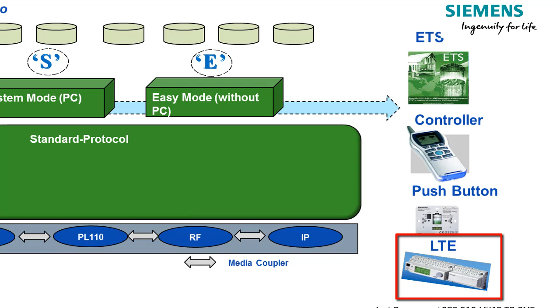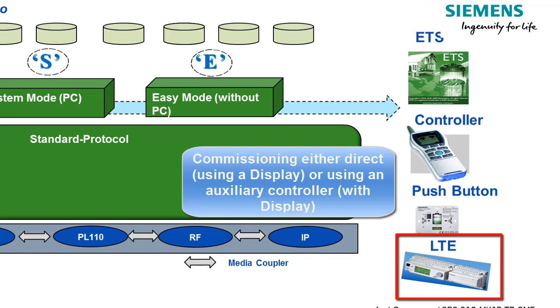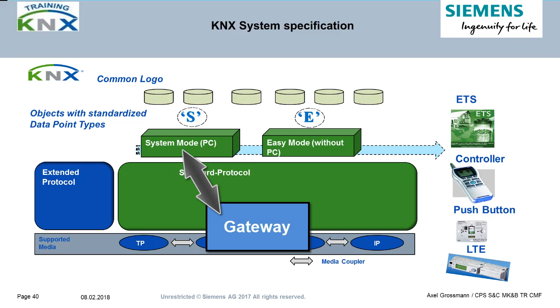3. LTE mode. LTE stands for Logical Tag Extended. It is also a kind of controller mode. However, the structure of the functional addresses, the so-called zones, is pre-designed. The subscribers having a display can be directly and independently assigned to their zones. Others require a commissioning controller with a display to assign the zones. LTE mode devices can be parameterized, but only by use of a computer tool. Devices with a different commissioning mode cannot communicate directly with one another, but suitable gateways to link such devices anyway are usually available.